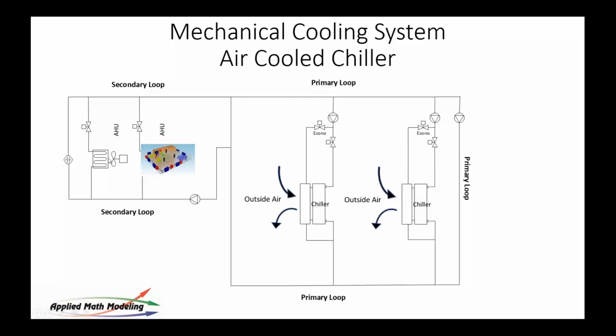This is just a fan coil representation here. These are fan coils in the room. That's how they work, and they are generally either, well, the older style used to be constant speed, more recently VFDs. So here's your primary loop. A pump drives the fluid around the primary loop, and then you have a secondary loop with a pump that drives here, and you use valves to allow the fluid to enter the rooms, and that controls the pressure deltas. There are pressure sensors that operate this. This is a fairly straightforward, common representation of how the system is done.